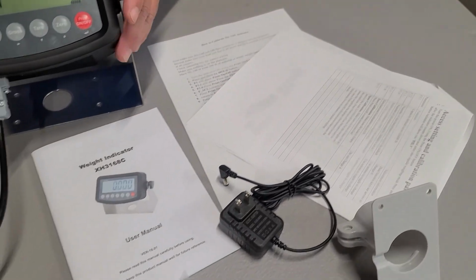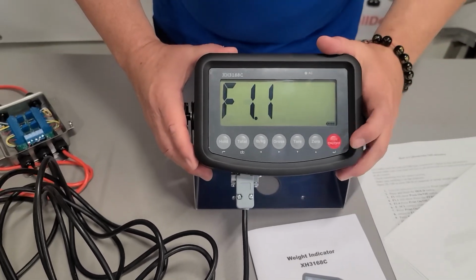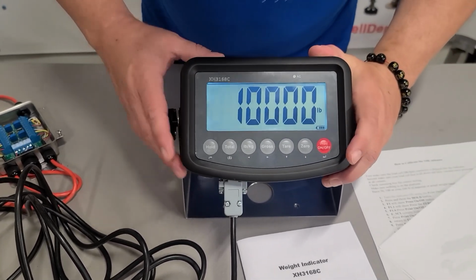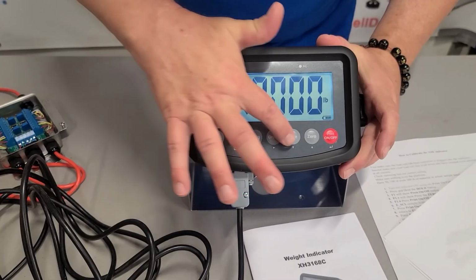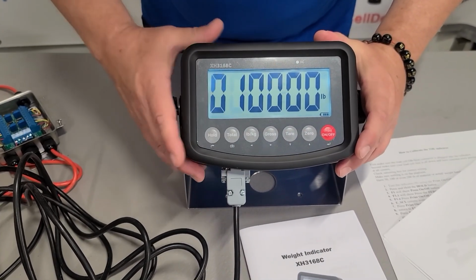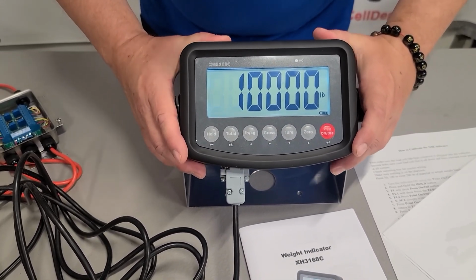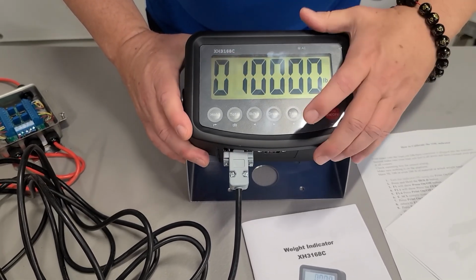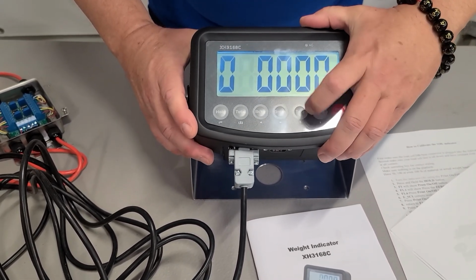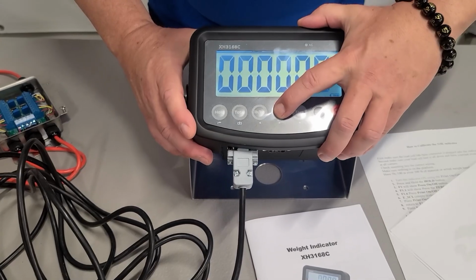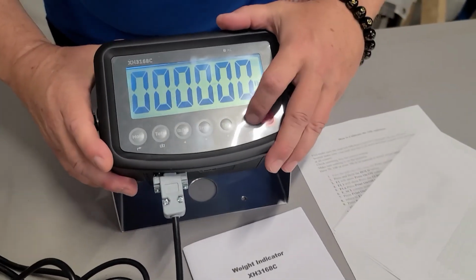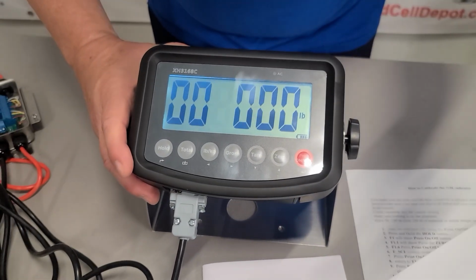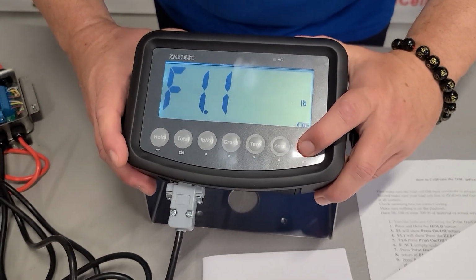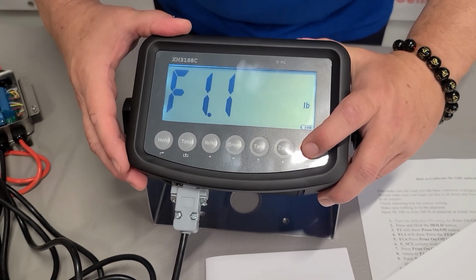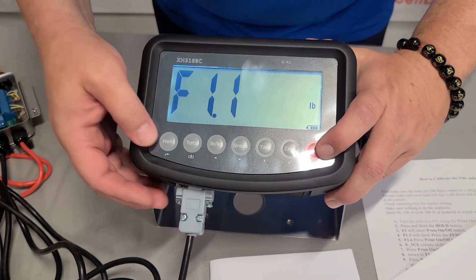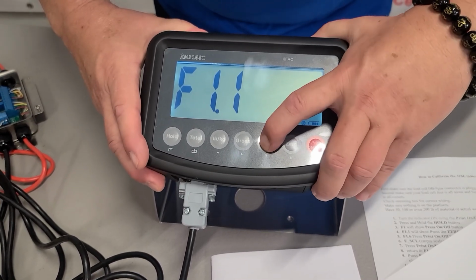So when you get into this function, F1.1 is your capacity. Now, I picked 10,000 pounds. You can use the arrow keys up and down to pick that particular capacity. We can change it if we like. We can move it over, and then we can change it to like 1,000 pounds. Then it goes back to F1. You can go to F2 by going up or down.